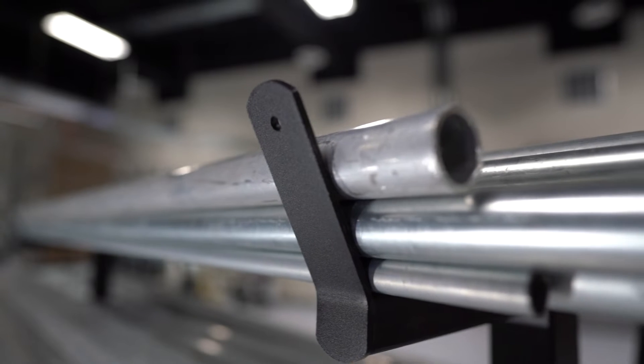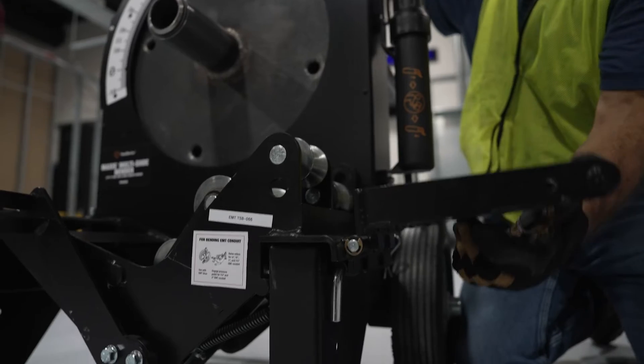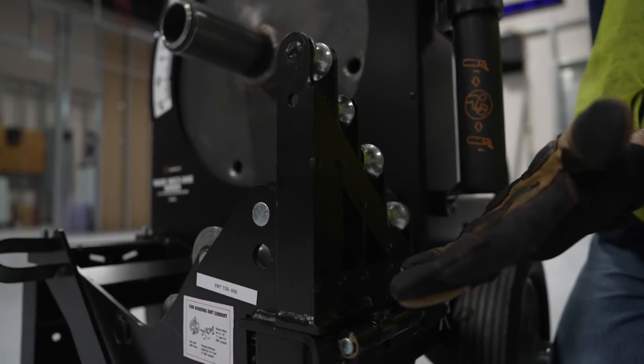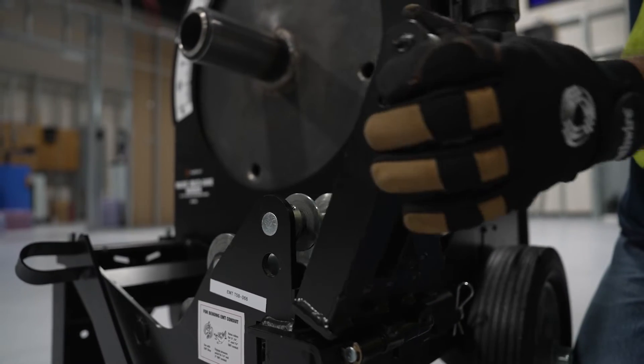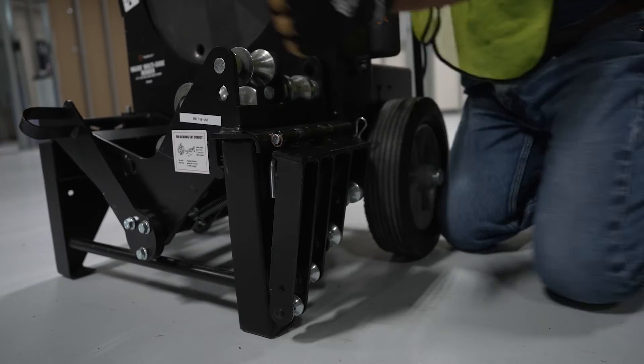Now if you're bending half-inch, three-quarter, one-inch, or inch and a quarter EMT conduit, the small rollers are placed in the up position like this. If you're bending inch and a half or two-inch conduit, the small rollers are not used and they can be left in the folded down position.